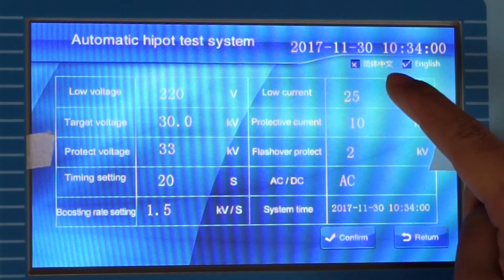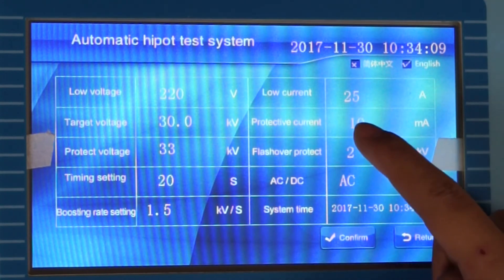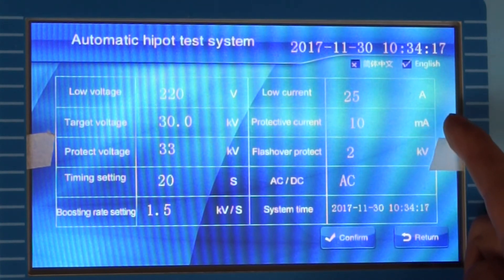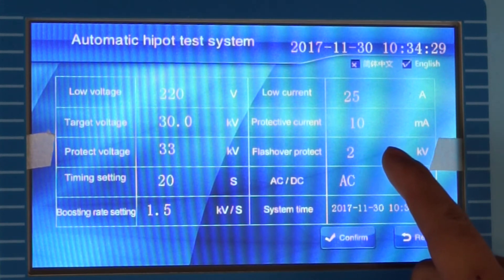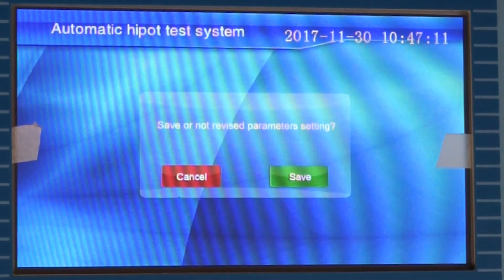Low current is the rated low-side current — it is 25A. Protective current is the over-current protection action value; according to your sample you can set it — we set 10 mA. Flash over protect is the flashover protection action value, usually set to 0.1 times the target voltage — so we set 3. We have finished setting the parameters.